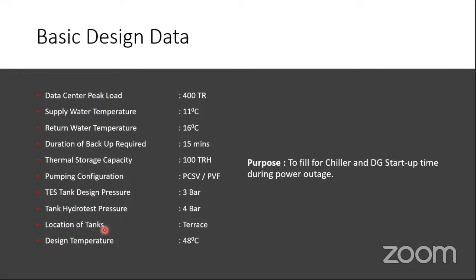The location of the tank is also something we should ask: where is it to be located, whether on the terrace, on the ground floor, in a basement, or outside. This will affect the design pressure of the tank, since static head is added, because generally a tank on the roof will have lesser design pressure and lesser working pressure. The design temperature is also important, from the insulation calculation perspective. So, what is the design temperature being considered?